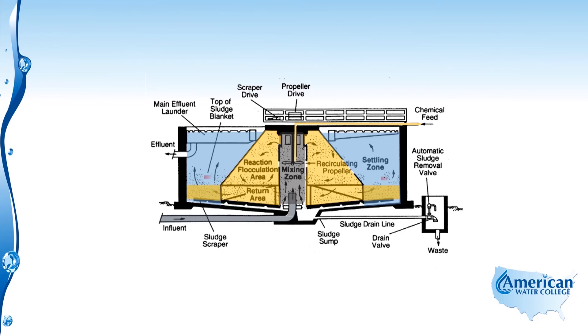The area where the sludge blanket occurs at the bottom portion is a very important control mechanism in the upflow clarifier, because it helps to filter the floc and clarify the water. Maintaining a proper sludge blanket through proper sludge wasting rates is very important for the operator to pay attention to.